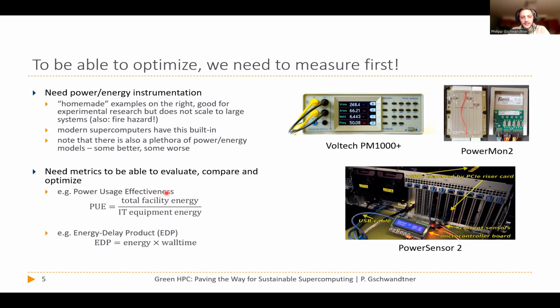One of them is power usage effectiveness, or PUE, which is basically an indicator of how efficient a data center or supercomputing center is. It's simply the fraction of total facility energy divided by IT equipment energy - how much energy the entire building consumes with all the cooling infrastructure, lights and so on, compared to the power needed for operating only the actual IT equipment. Ideally the PUE is 1. We usually never reach that because there's always some overhead, but these days we're in the 1.0-something realm, which is quite efficient. Thirty or forty years ago you might have a PUE of 2, meaning half the energy was spent on cooling the system and only half on operating it, which was really, really bad.